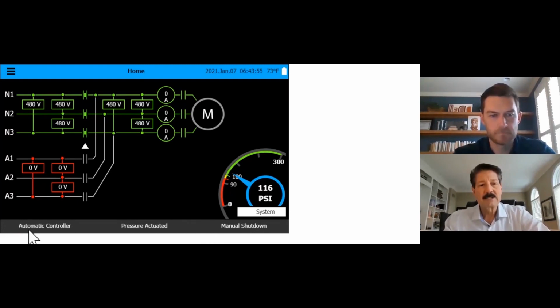On the bottom left side, it says automatic controller. In the middle bottom, pressure actuated. Bottom right, manual shutdown. All these items I'm talking about, what type of controller is it? Is it pressure actuated? Is it in manual shutdown? The cut-in pressure of 90 psi, the cutout at 100, the system pressure 116, an ammeter, voltmeter. These are all required by code.